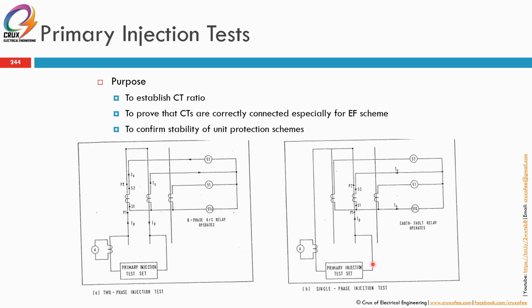Okay. So this is primary injection test for single phase injection. It means you just inject into one phase. So one side will be connected to P1, the other side will be connected to the P2 side of the primary injection. In this case, if you're injecting here at yellow phase, since yellow phase has no 51 IDMT, it will trigger only 51G, which is the earth fault. But if you're injecting single phase at the red phase, 51 will pick up as well as 51G, depending on the pickup current.